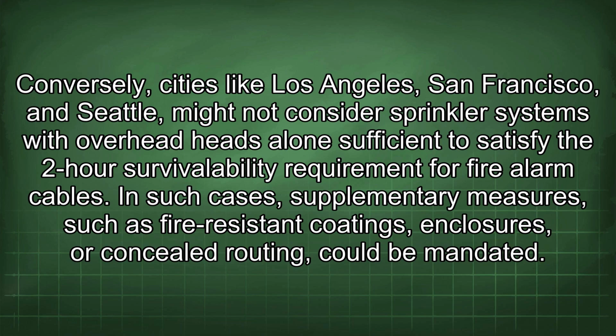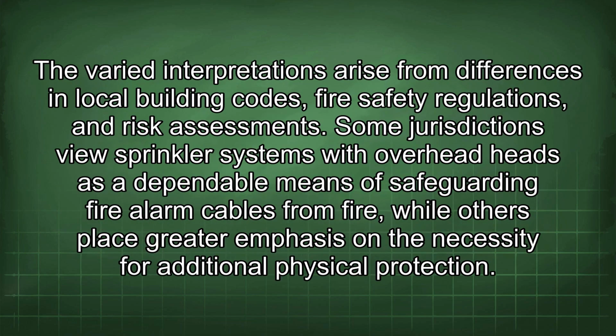Conversely, cities like Los Angeles, San Francisco, and Seattle might not consider sprinkler systems with overhead heads alone sufficient to satisfy the 2-hour survivability requirement for fire alarm cables. In such cases, supplementary measures such as fire-resistant coatings, enclosures, or concealed routing could be mandated. The varied interpretations arise from differences in local building codes, fire safety regulations, and risk assessments. Some jurisdictions view sprinkler systems with overhead heads as a dependable means of safeguarding fire alarm cables from fire, while others place greater emphasis on the necessity for additional physical protection.